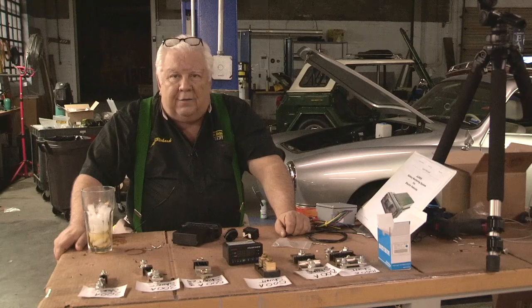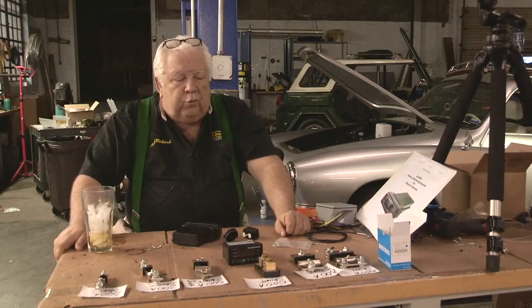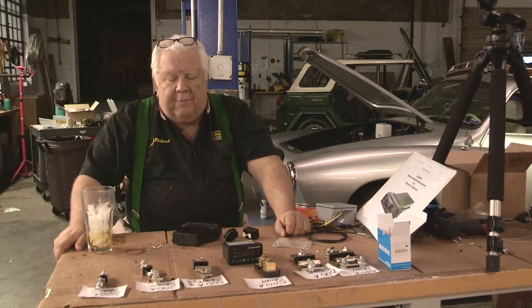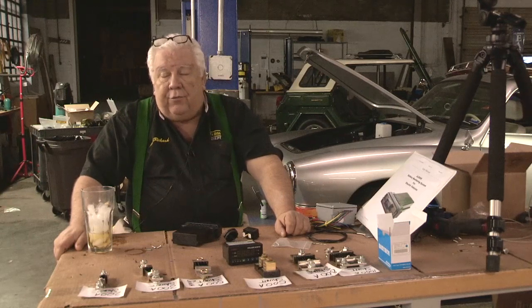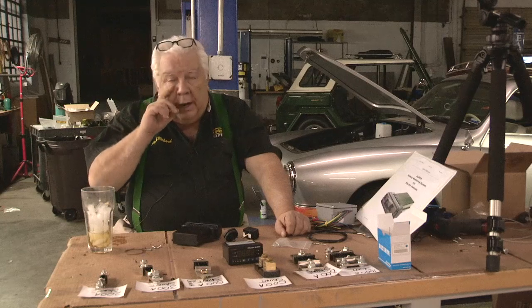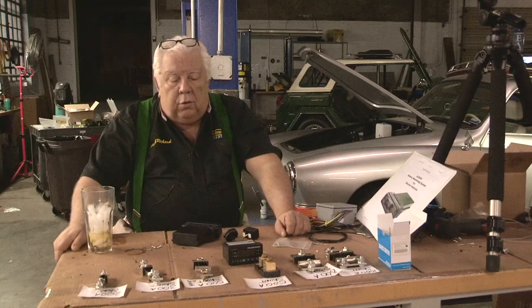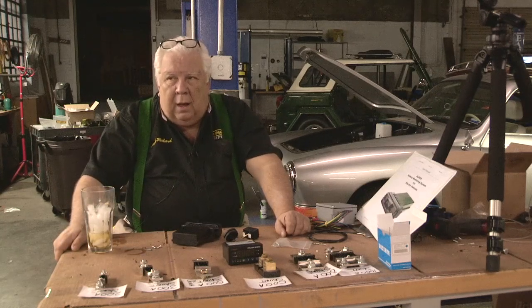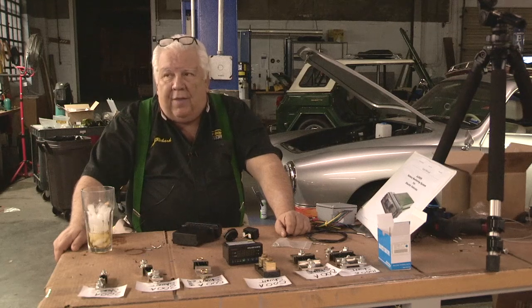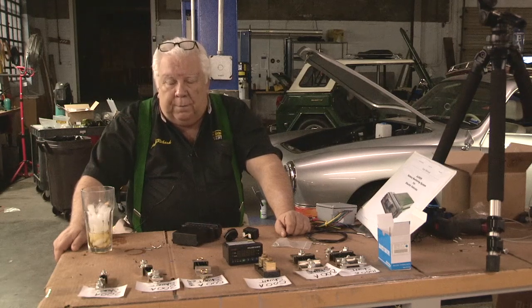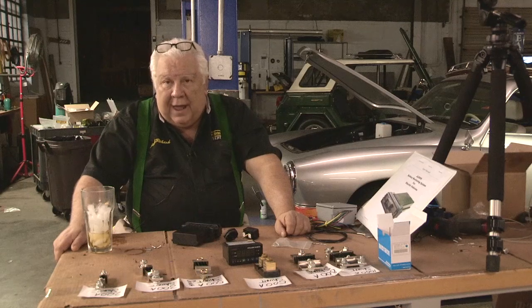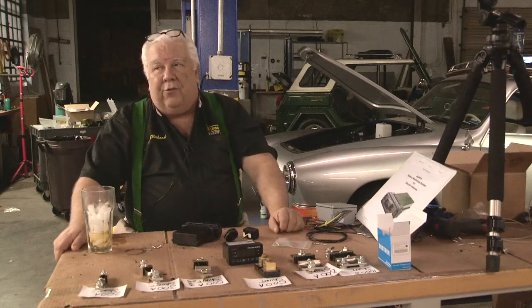In actual practice, you can double it, and we have routinely done so, taking a 500 amp shunt and running 1000 amps through it. You get a little more heating, and so your accuracy at 1000 amps is not quite as good. On the other hand, at 1000 amps, how much accuracy do you need?